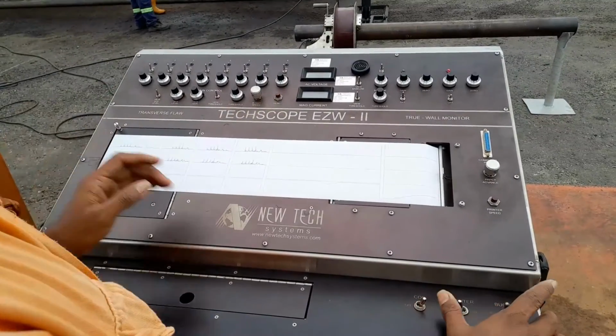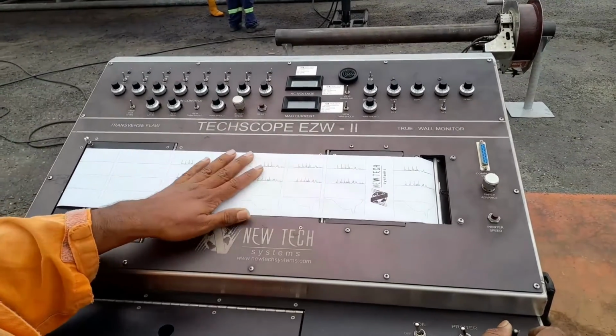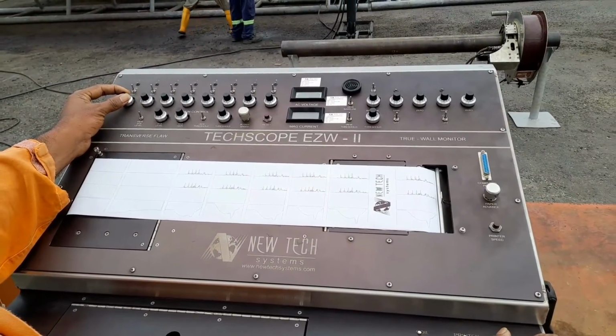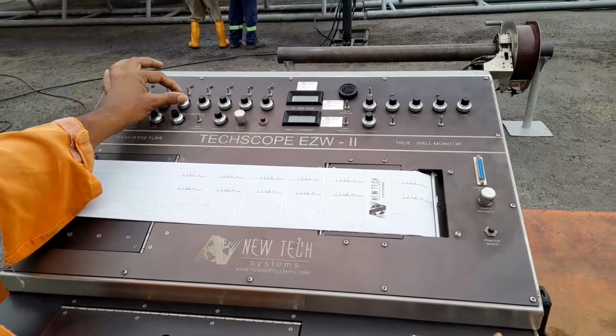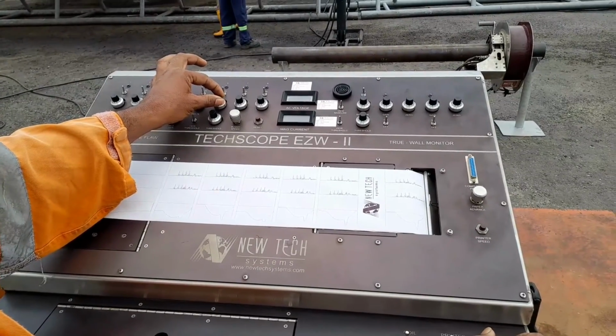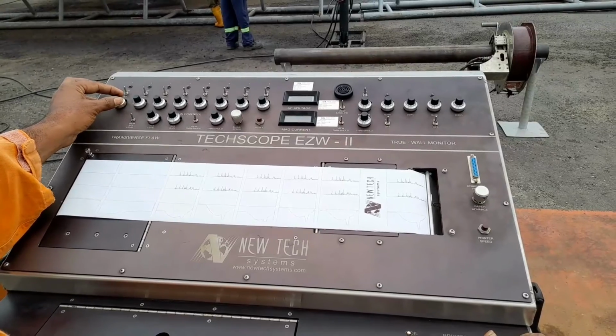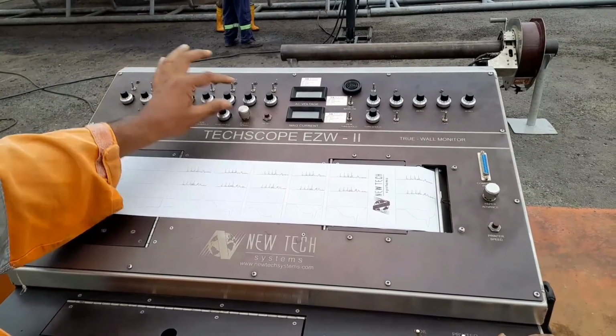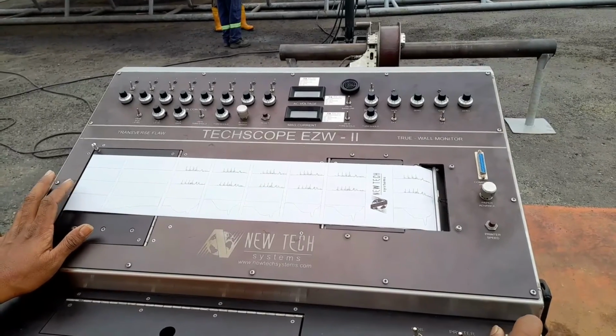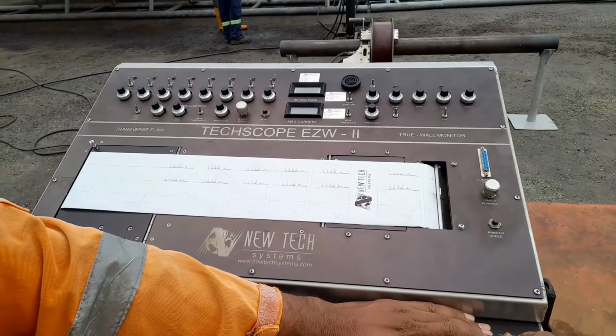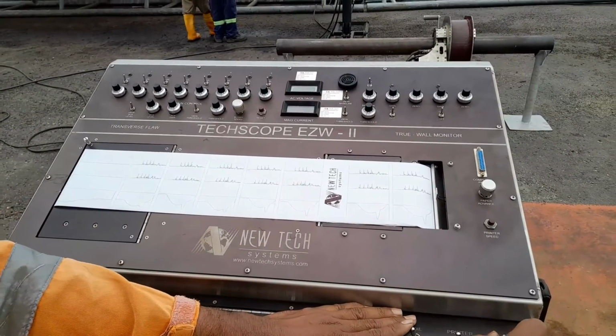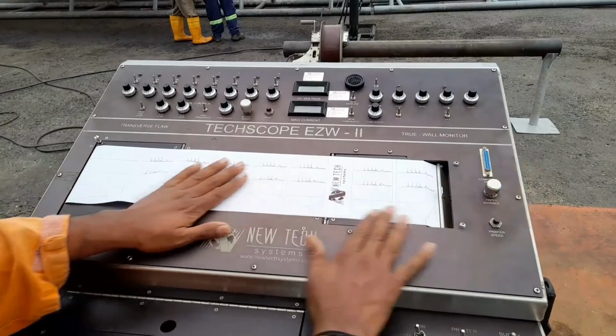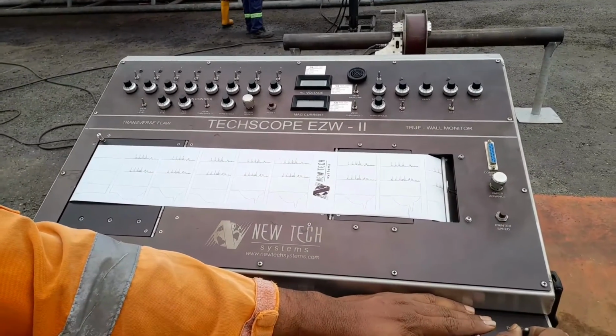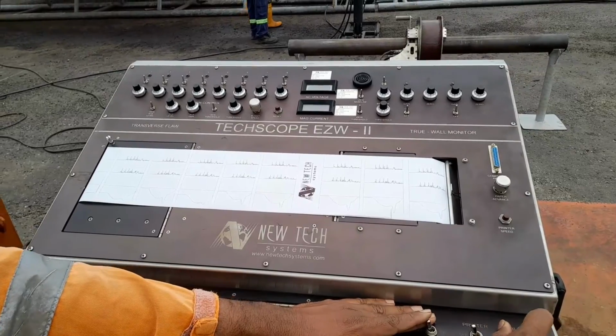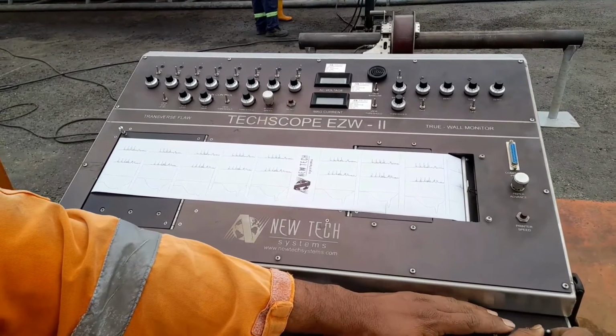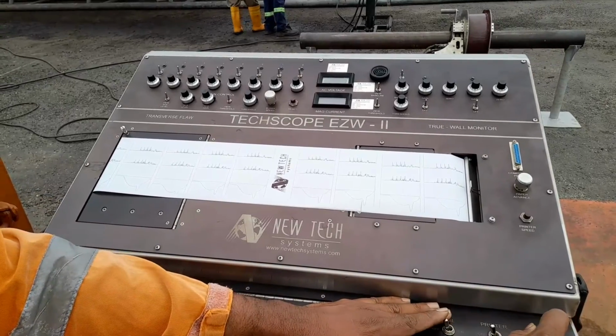Give the gain value 2, 3 or 5 or 6 something. Adjust the zero clockwise. When the beep sound is off and light is off, keep that position. Then you have to run. You can get a perfect wall monitoring calibration graph. If the graph is not passing the threshold line, you have to increase the gain a little bit. It's the easiest method for the wall monitoring system.